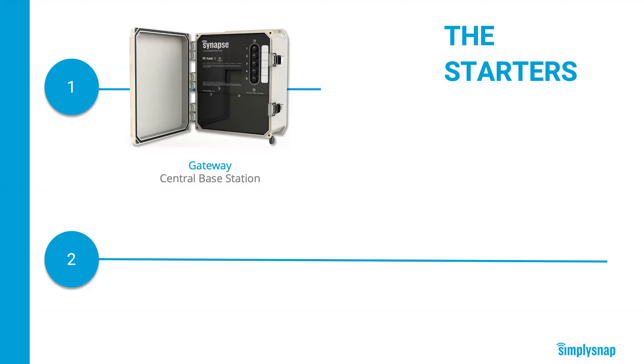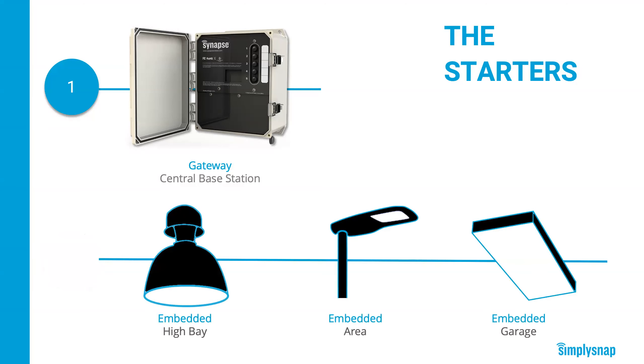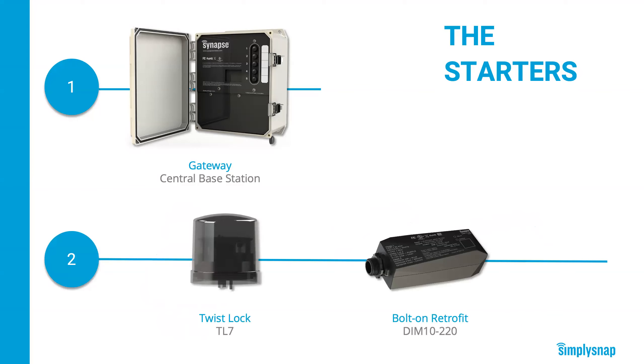One gateway typically manages up to about 500 lights. We've worked hard to get our controllers embedded in high bay, area, and parking garage fixtures from the leading fixture manufacturers so you can put Simply Snap into a whole host of different applications. If you have a fixture with a NEMA socket or a retrofit project, we have solutions for those too. We have a twist lock controller in 277-volt and 480-volt versions with built-in photo cells that can integrate with a motion sensor and fit any standard seven-pin NEMA socket typically found on a parking lot or street light fixture. For LED retrofits, we have an IP65-rated controller, the DIM10-220, that you can pull mount or put in the half-inch nipple threaded connector on the fixture.